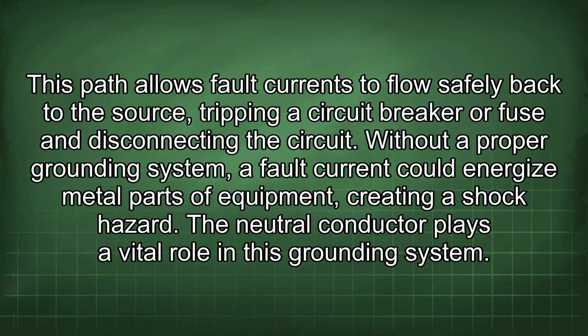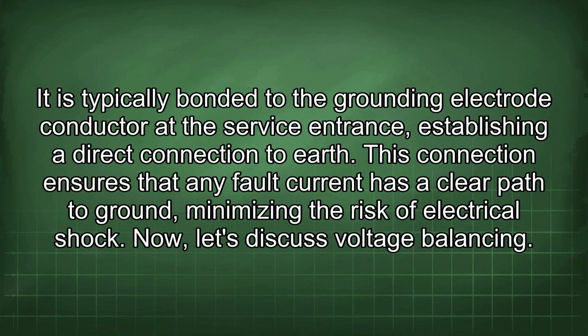The neutral conductor plays a vital role in this grounding system. It is typically bonded to the grounding electrode conductor at the service entrance, establishing a direct connection to earth. This connection ensures that any fault current has a clear path to ground, minimizing the risk of electrical shock.